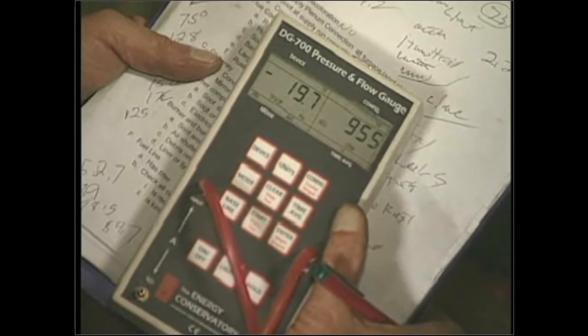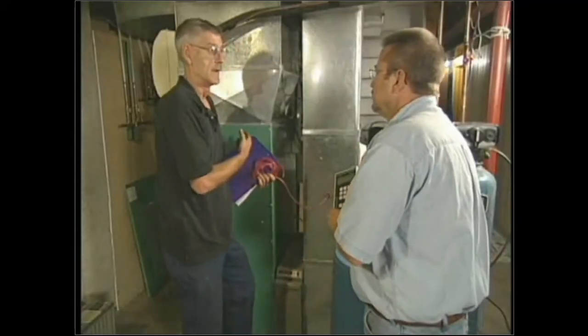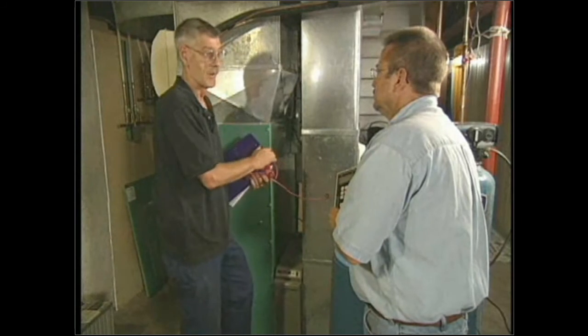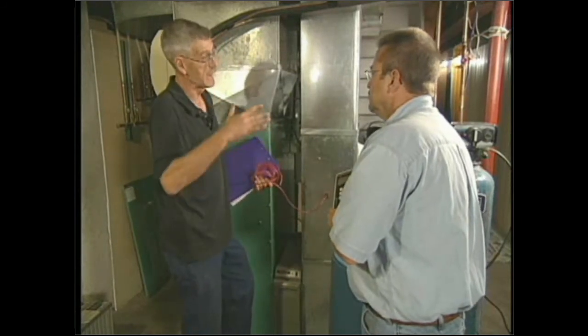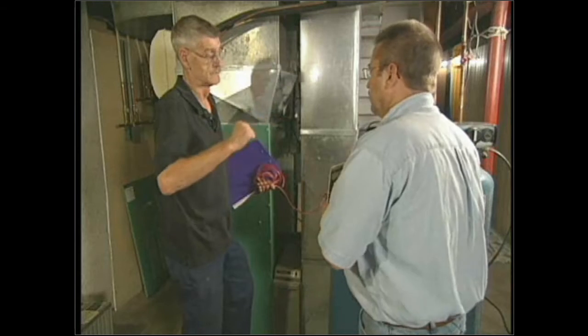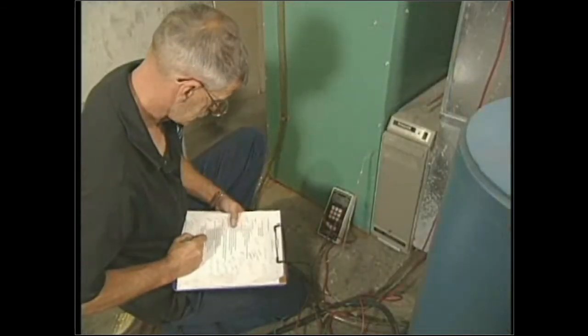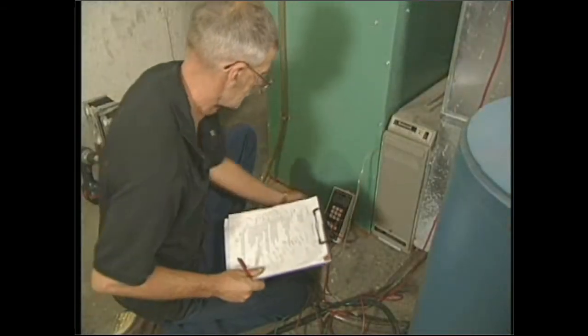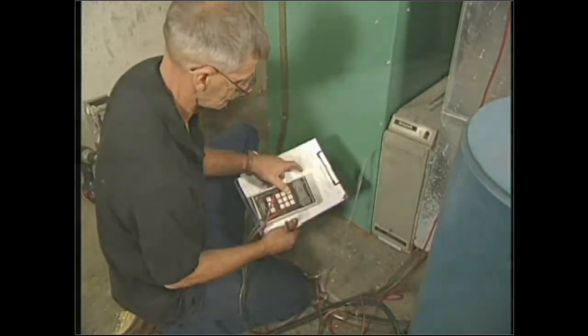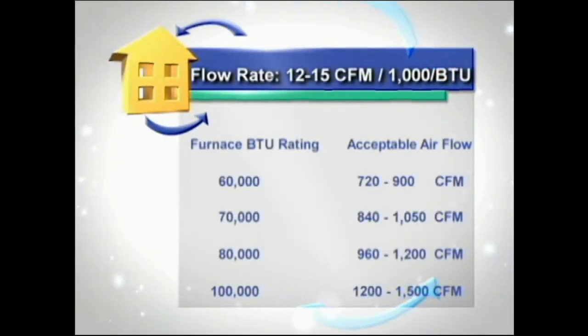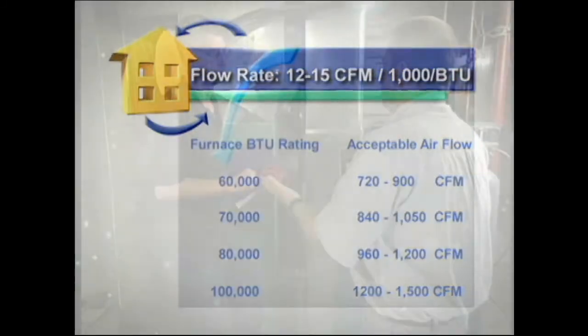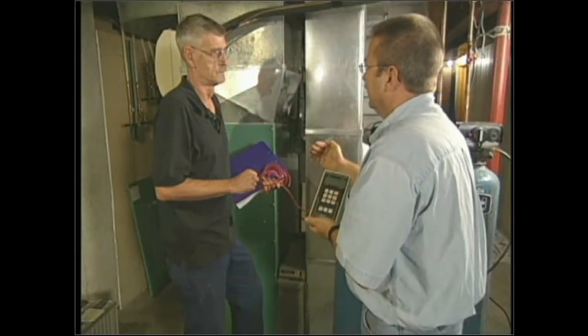Now, we're fortunate this one's running about 900 CFM. And this right now is probably burning about 90,000 BTUs. So we're right at that point where we should be. So it seems to me that you take these numbers, you use a manometer to get the different readings. Yep. You document those readings, compare it to the PMI, and that'll tell you if we're within our parameters. It also tells us if we need to make some adjustments, like on our temperature rise. If our temperature rise is slightly high, we can increase our airflow up a little bit and bring our temperature rise down.